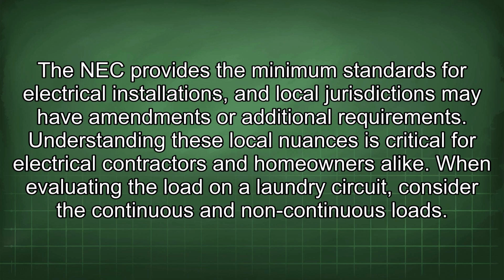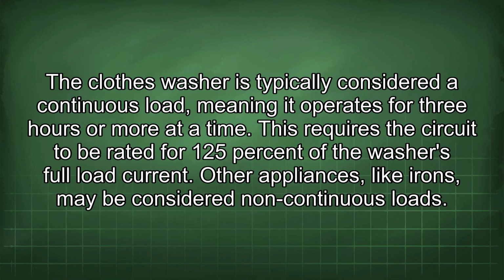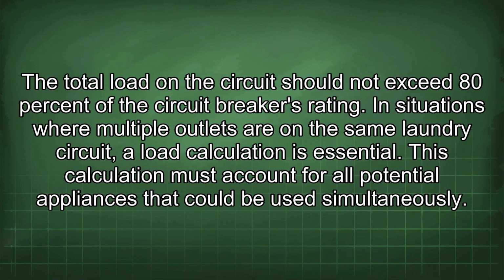When evaluating a load on a laundry circuit, consider the continuous and non-continuous loads. The clothes washer is typically considered a continuous load, meaning it operates for 3 hours or more at a time. This requires the circuit to be rated for 125% of the washer's full load current. Other appliances, like irons, may be considered non-continuous loads. The total load on the circuit should not exceed 80% of the circuit breaker's rating.